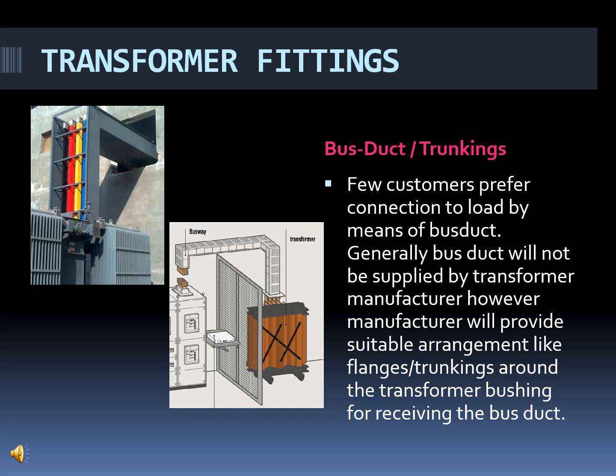In this slide, we will learn about the bus duct or trunking of the transformer fitting. I have enclosed two images. You can observe how the bus duct has been connected to the transformer and to the switchgear. Some customers ask for the connection to load the transformer through a bus duct, not through cables. Generally the bus duct is not supplied by the transformer manufacturer. However, the manufacturer will provide a suitable arrangement for installing a bus duct at your site, such as flanges or trunkings around the transformer bushing to receive a bus duct.